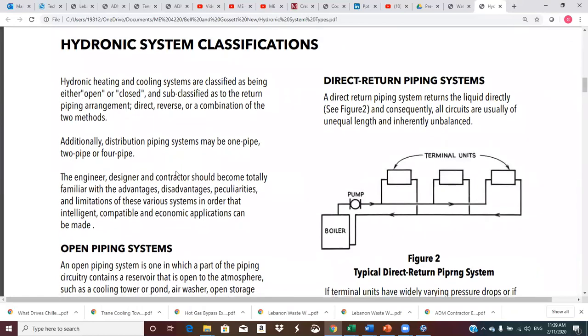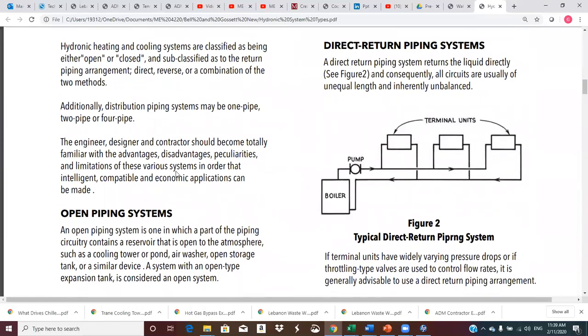Okay. Now let's talk about direct return piping. So you see here we have what we would call probably 3 zones, or it could be 3 terminal units in the same zone. We're not showing controls yet, so you don't know, is there one thermostat controlling all 3 of these, or does each one have its own thermostat? We don't know, and that's not the purpose of this discussion, so we're not worrying about it.